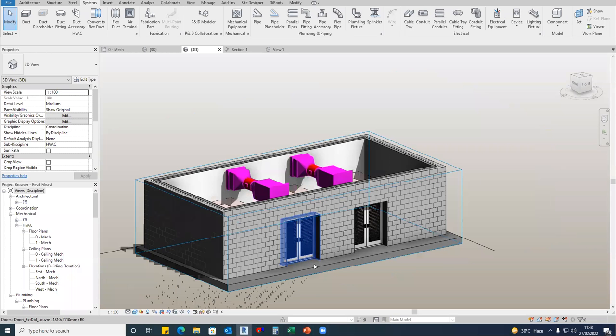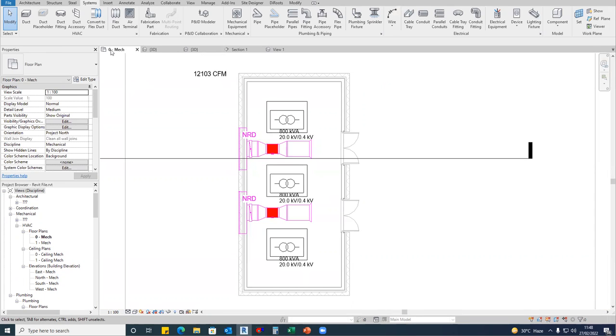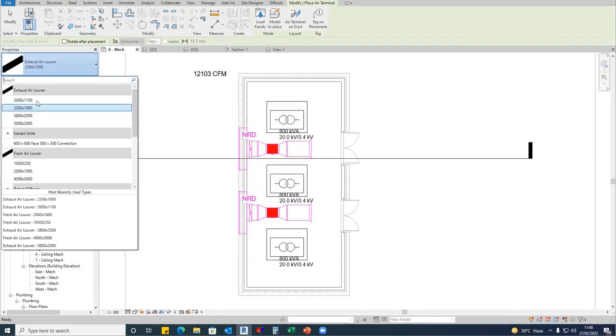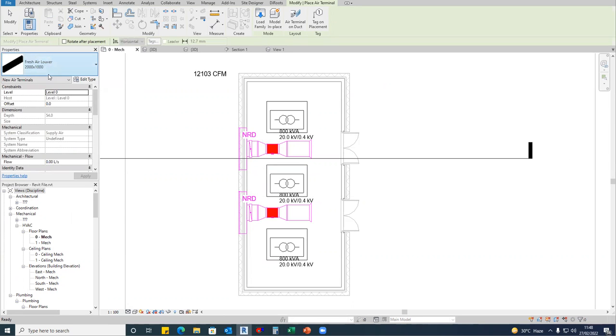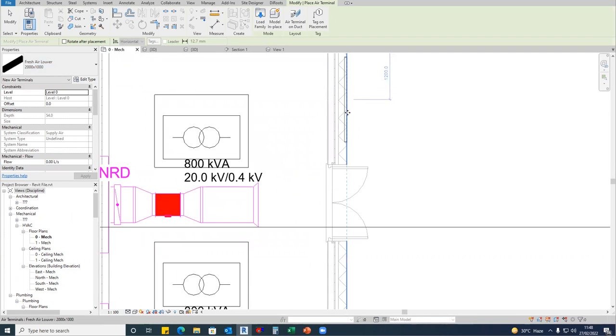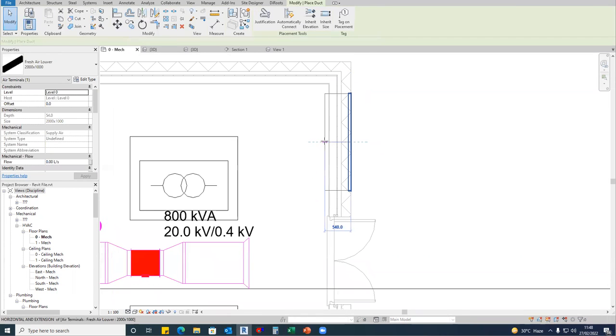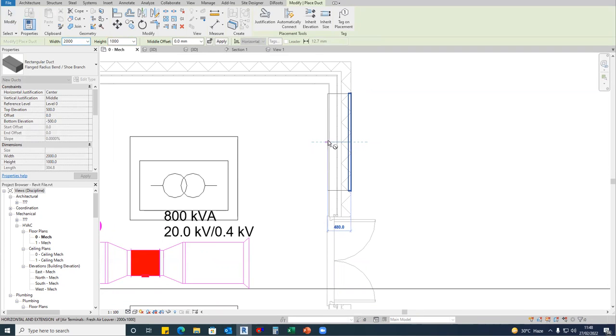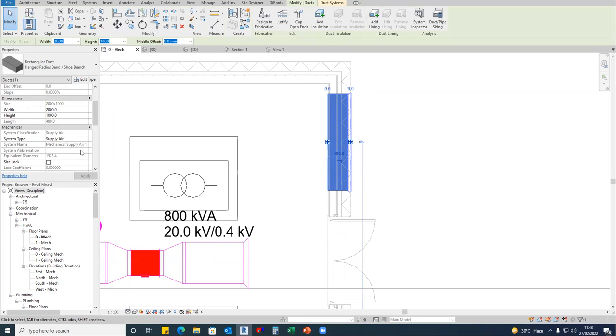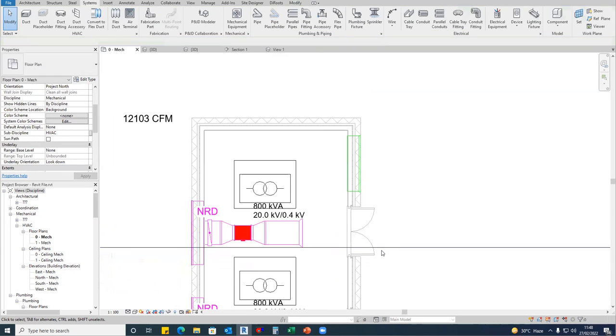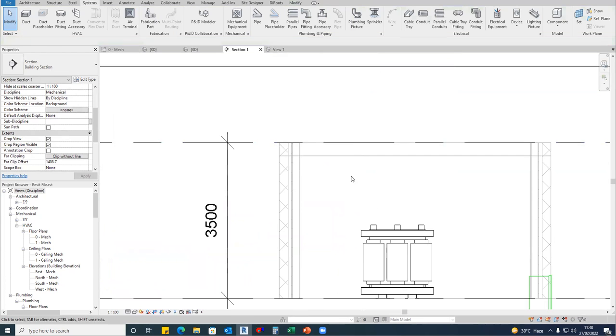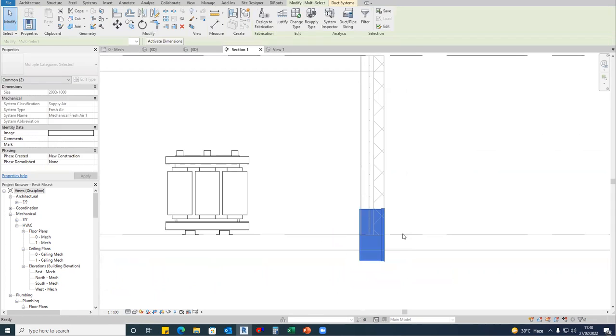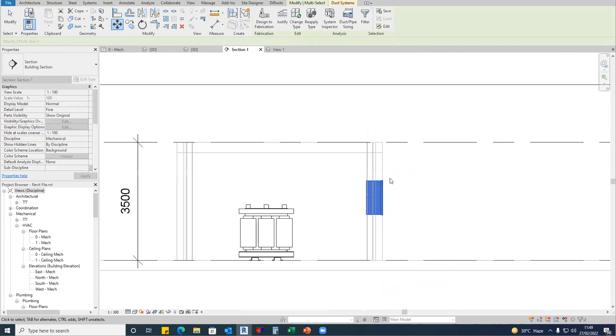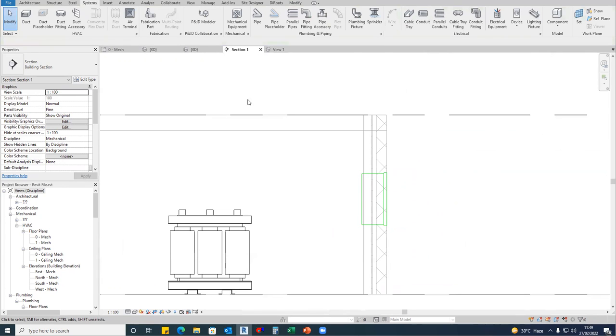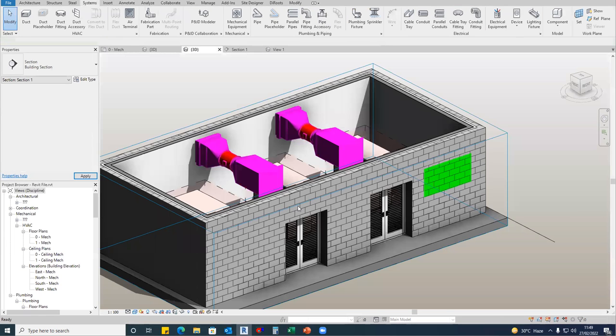I'll go to the model, go to the plan view, and I'll select one air terminal, fresh air louver. Oh, I have a 2 meter by 1 meter fresh air louver over here, and I'll place it over here. And put an exhaust, sorry, fresh air. This is the plenum. Make the system as fresh air. Okay. Make sure to check the elevation. Okay, fine. So this you can align with the door height. So it must look good. Let me check in the 3D view itself.